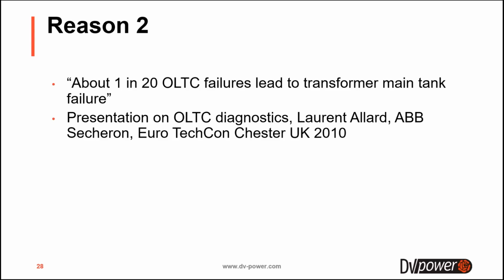An OLTC failure, if only the OLTC fails, is not such a big issue. You can repair it, you can easily replace it. It doesn't cost as much as a transformer failure, but the problem is that an OLTC failure can lead to complete transformer main tank failure, and roughly 1 in 20 OLTC failures can lead to complete transformer failure. That can represent a big problem, and of course it costs a lot.